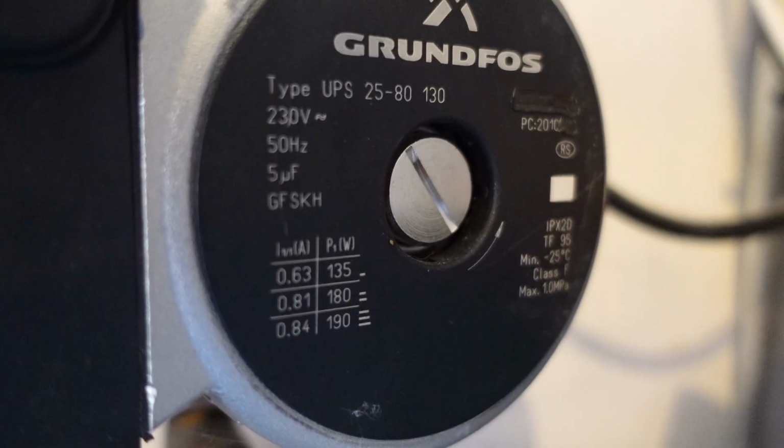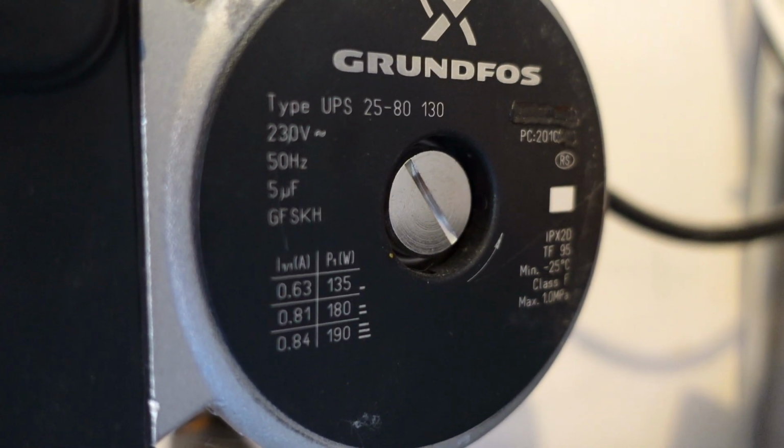Based on a worst case, I'll try and work out my index circuit and whether the pumps that we've got, because they're good, quite heavy duty pumps, can be utilised. If we can run the system with one of those, great. But I need to work out the math now to see if that is possible.